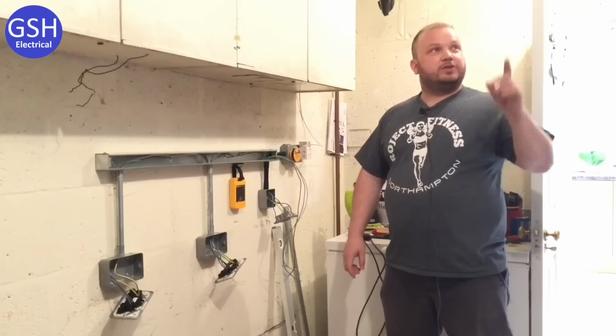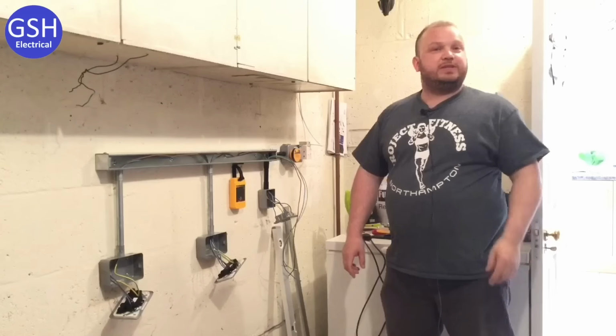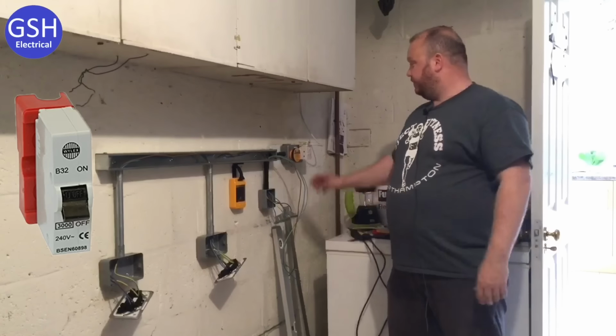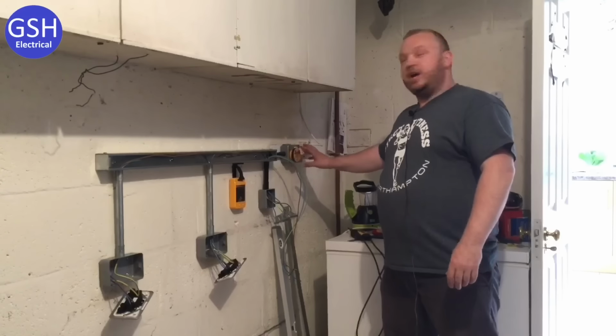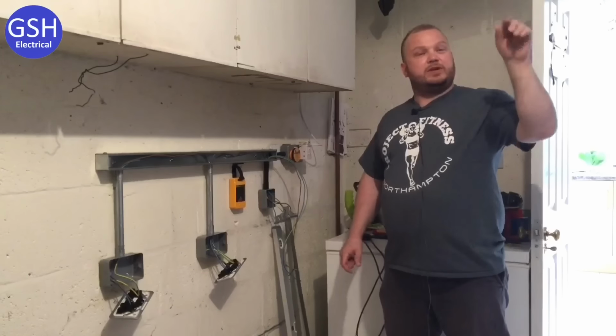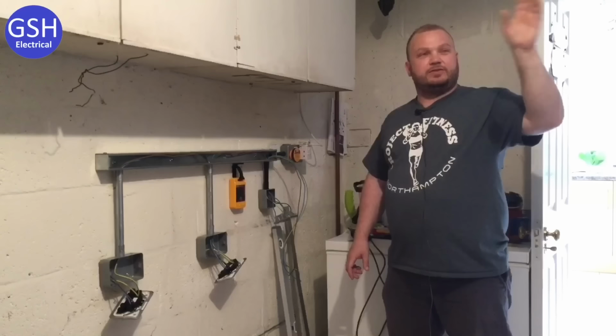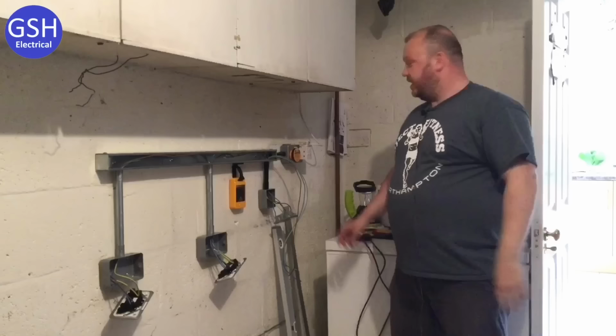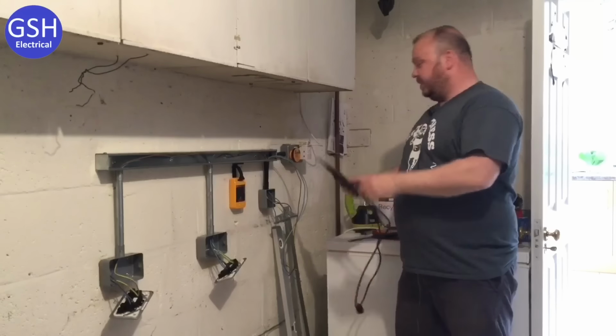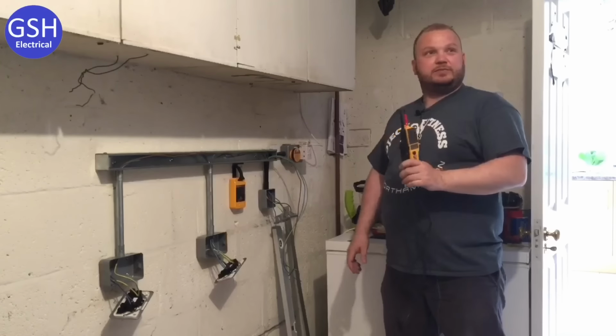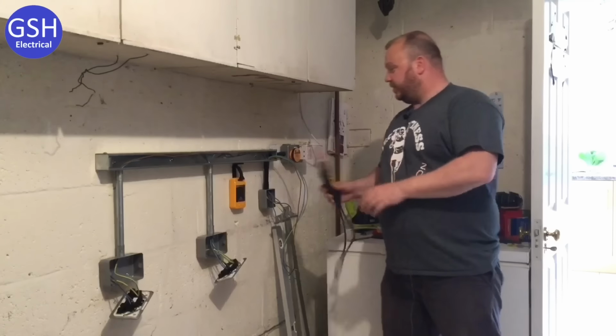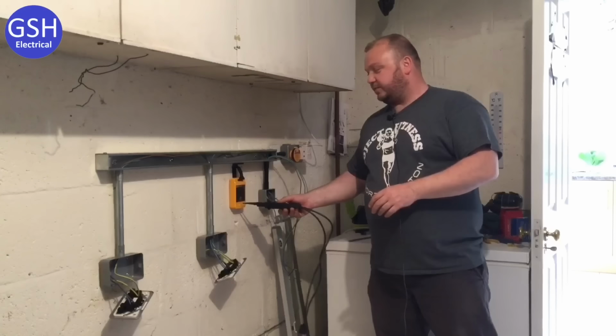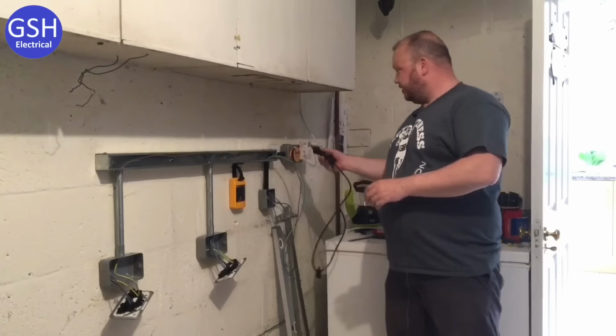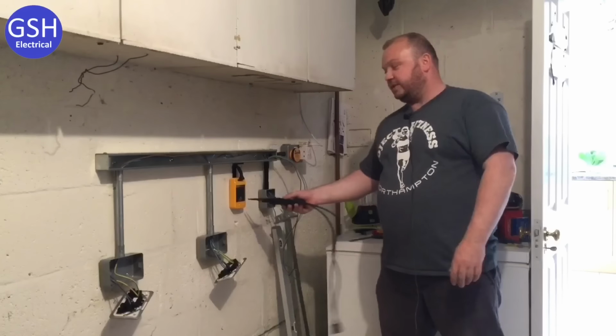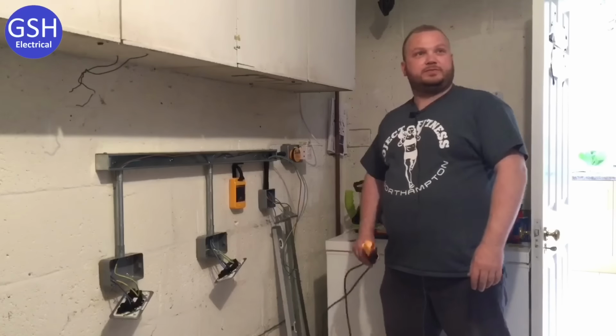What would you like me to do? I'd like you to switch off the breaker, please. Okay. So now we've worked out that is the right circuit. We're going to now isolate. We're going to use a locking off kit to make sure that is locked off safe. And we're going to go into the back of this with my voltage tester and check it's dead. Before you use that voltage tester, are you going to do anything with it? I'm going to use the proving unit to prove that it's working, and I'm going to check here to make sure it's dead, and then I'm going to test the voltage tester again after. Brilliant. That's great, Mark.